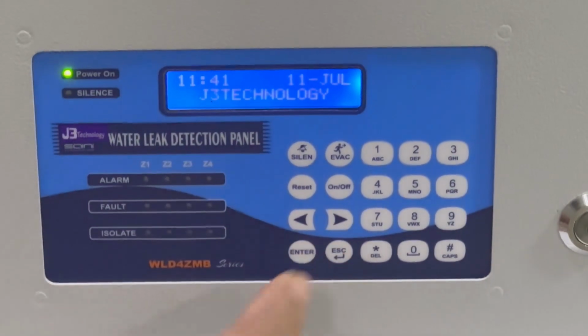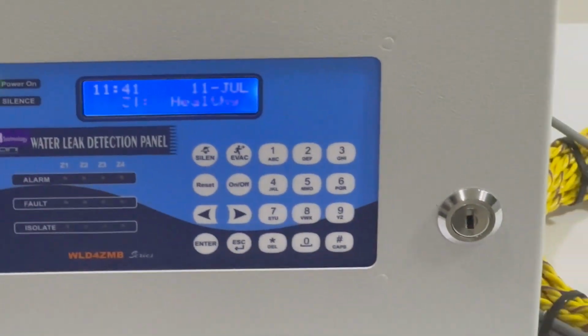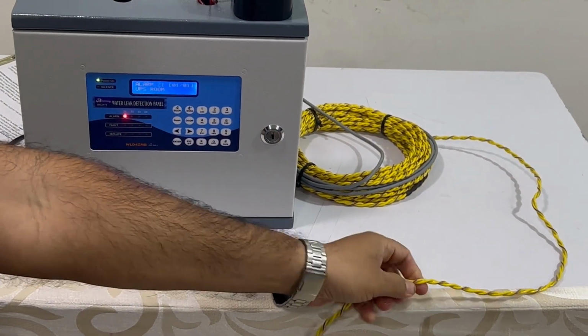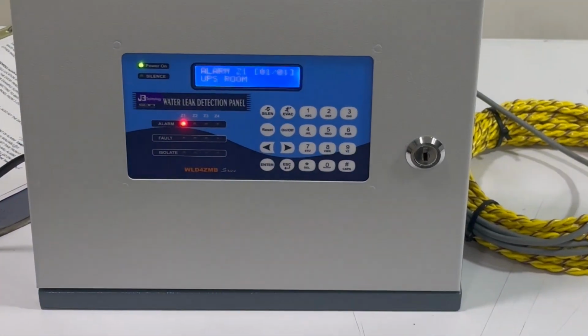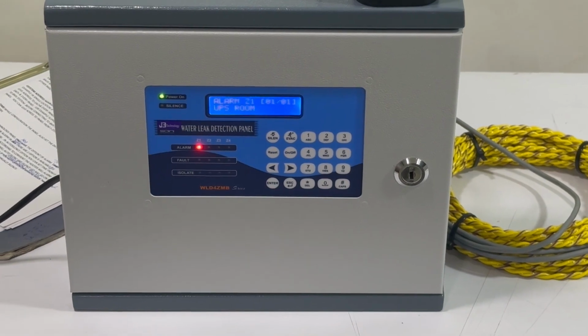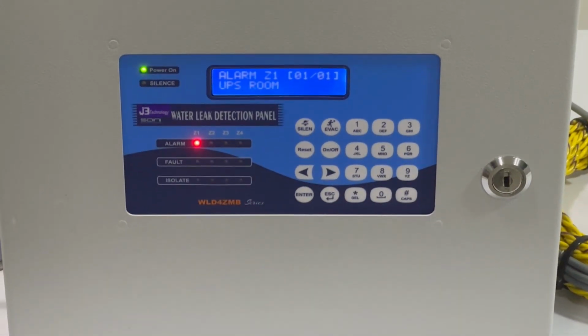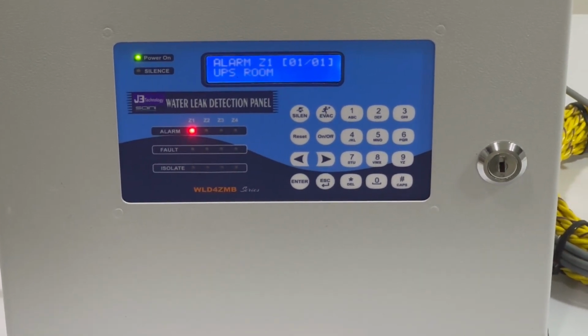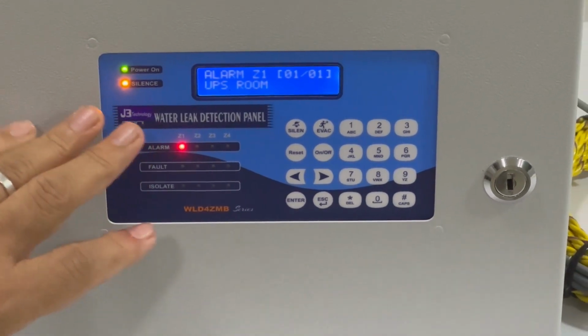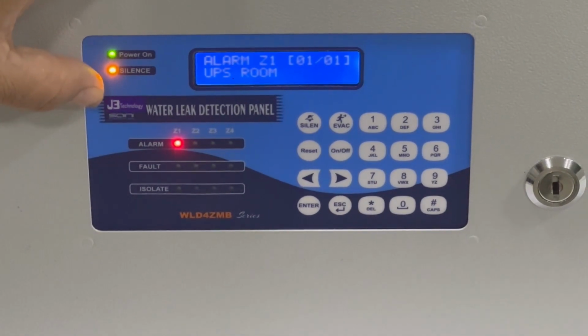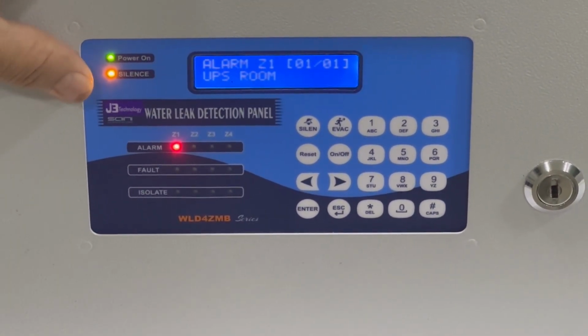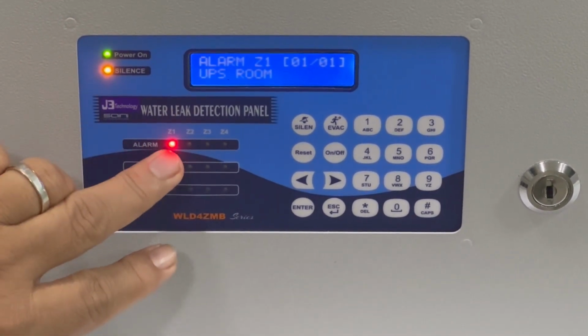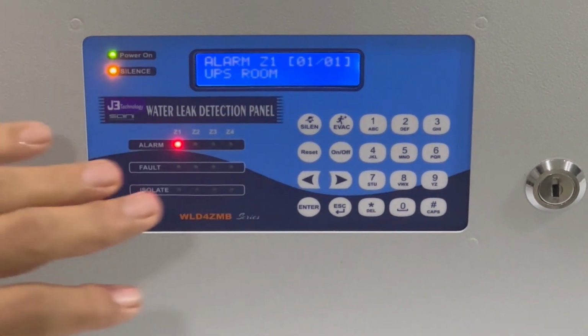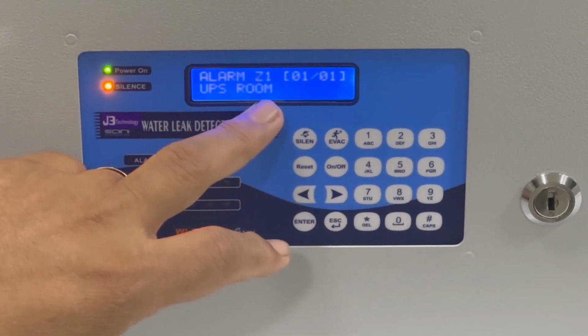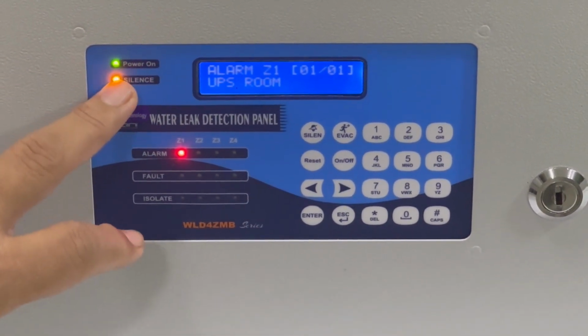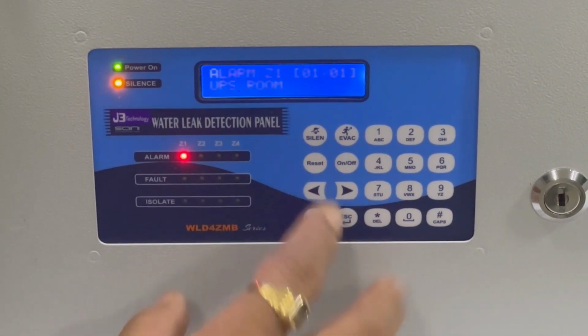Now I will generate the alarm and you can check, it will automatically stop. See, the alarm is gone. After 20 seconds it will turn off. The panel gets silenced after 20 seconds. See, the panel gets silenced automatically after 20 seconds. This is a special feature which is available in our panel only. But the indication and the display will still show you the alarm in the UPS room. As we defined zone 1 as the UPS room, you can check. It is showing the UPS room. There is an alarm, and the panel gets silenced. Okay, so again I will reset this manually.